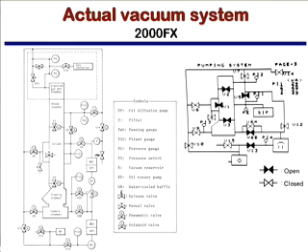Yes, sir? In Lab 1, you accidentally hit one of the valves. Yeah, actually in Lab 1 for one group, on the 2000 FX, the camera chamber, there's a little lever to open up the film camera, and it's not too far from your knees. And I banged it with my knee and opened that up. So what that does is it initiates a sequence.